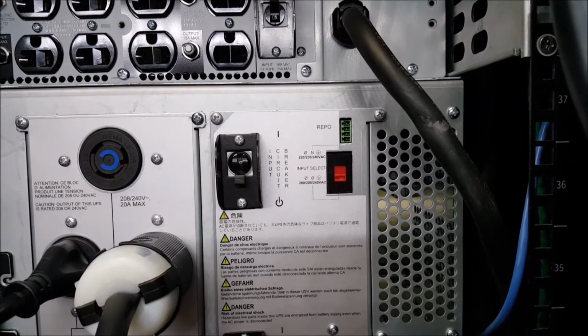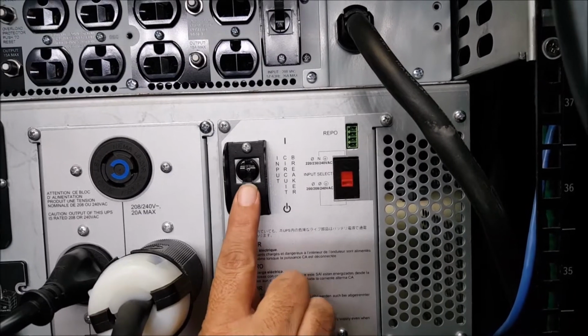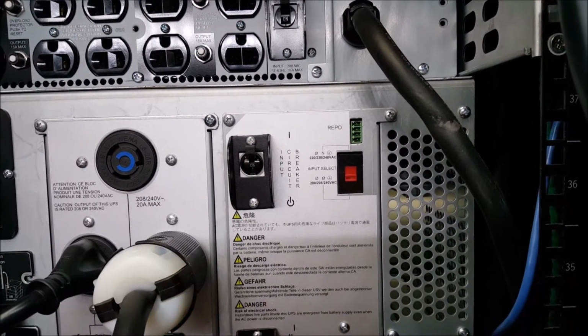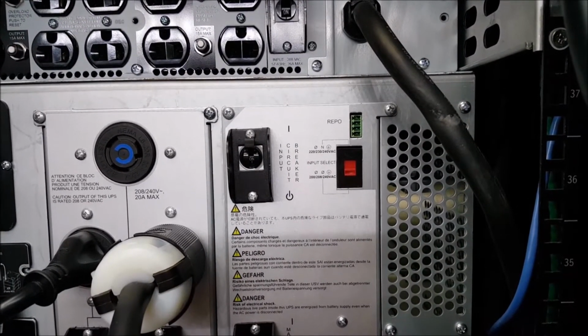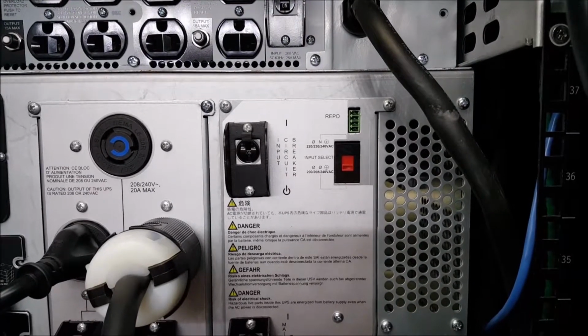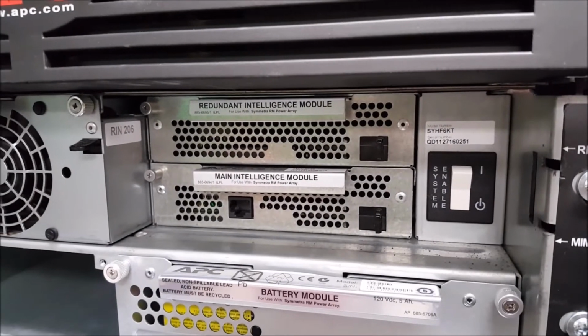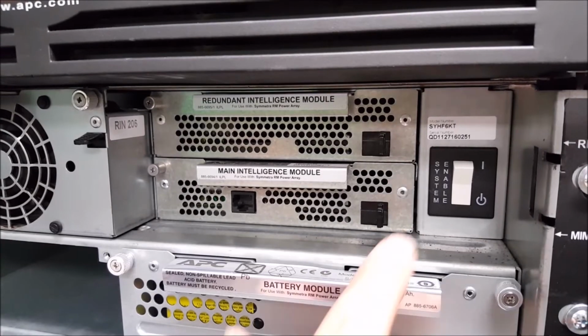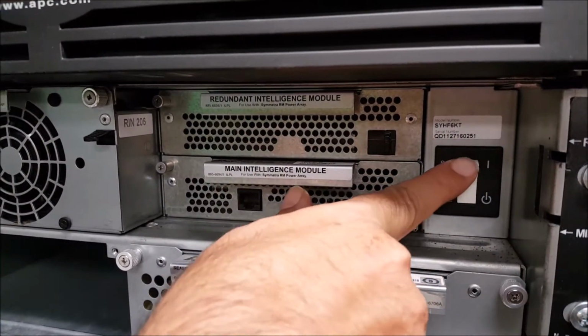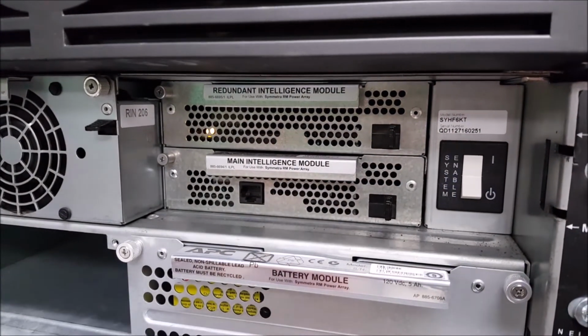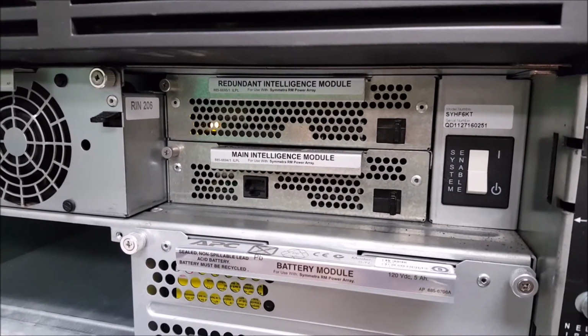Next, you'll want to turn on the input circuit breaker on the back of the Symmetra RM UPS, as well as any upstream breakers that might be feeding the unit. With all circuit breakers feeding the UPS turned back on and the battery modules reconnected, you'll next turn on the Symmetra RM UPS by turning on the system enable switch located to the right of the intelligence modules.